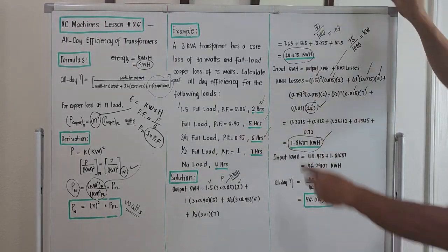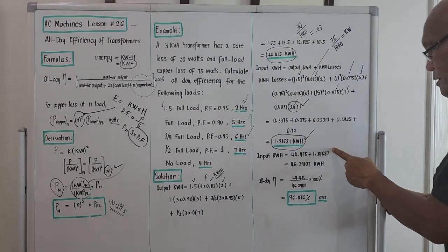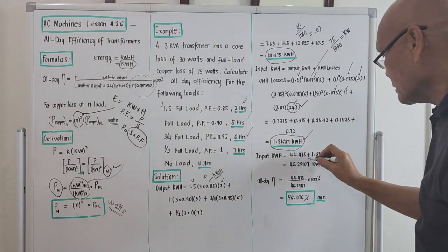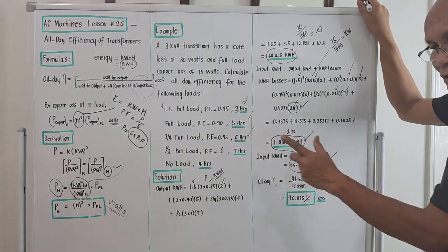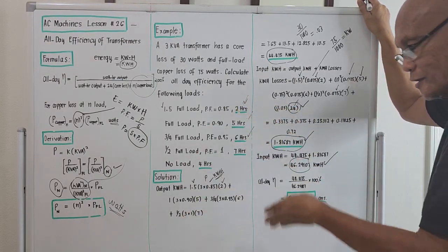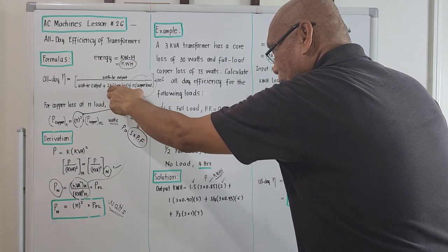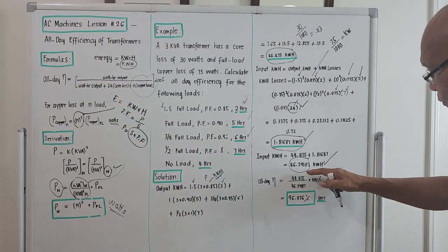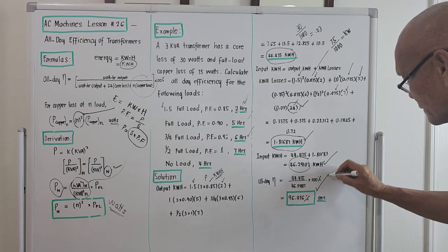The input kilowatt-hours are 44.475 + 1.81687 = 46.29107 kilowatt-hours. The all-day efficiency is therefore 44.475 divided by 46.29107, which equals 96.076 percent.